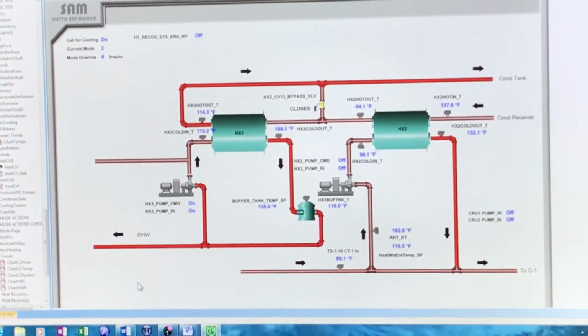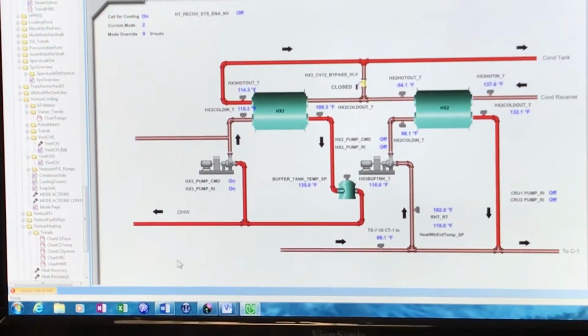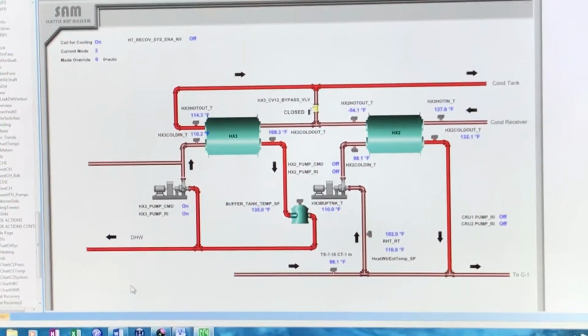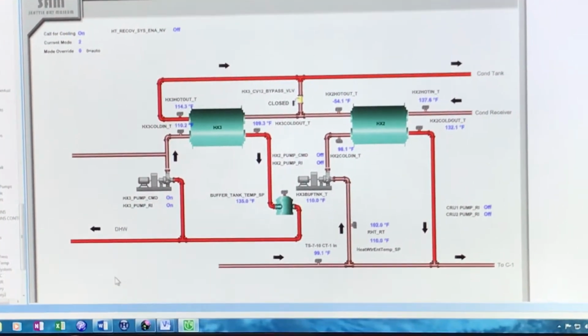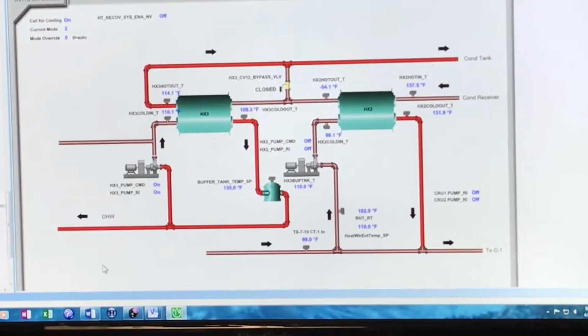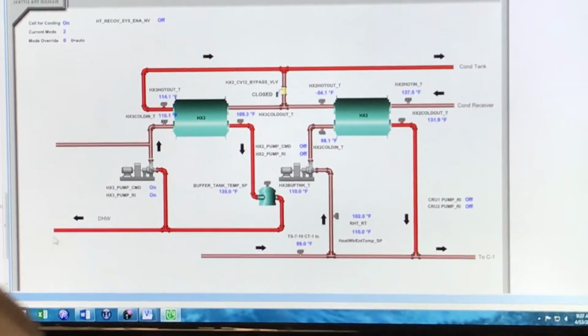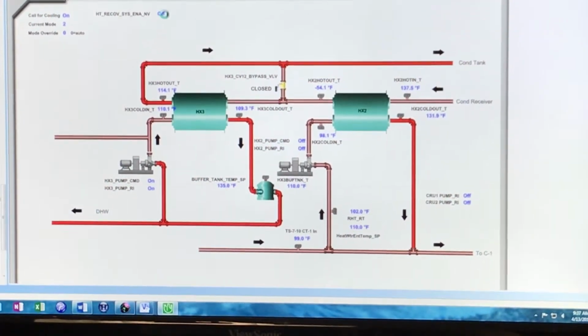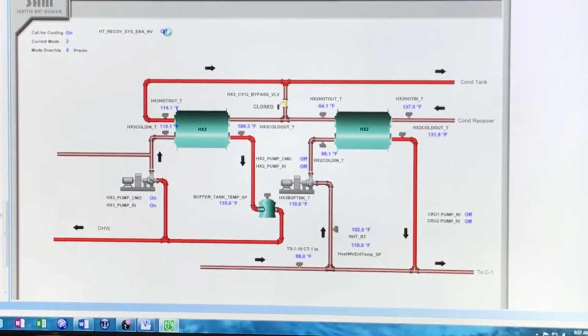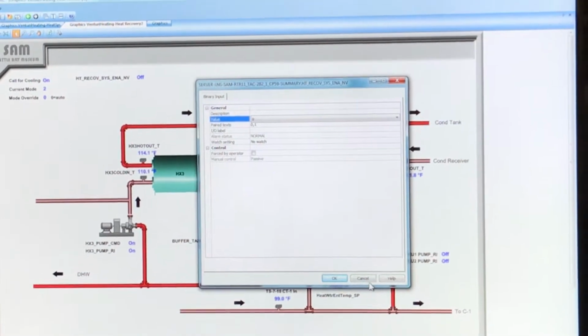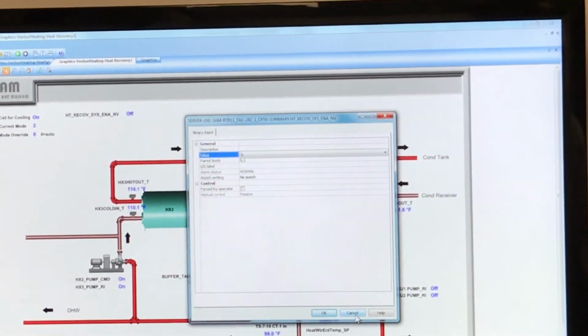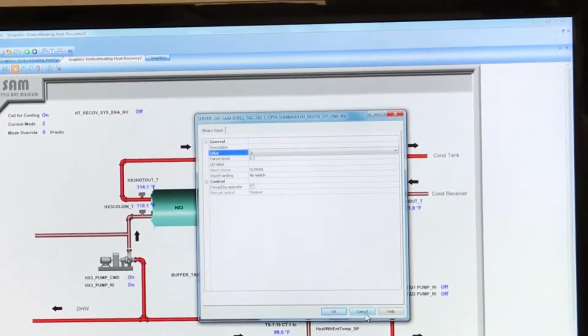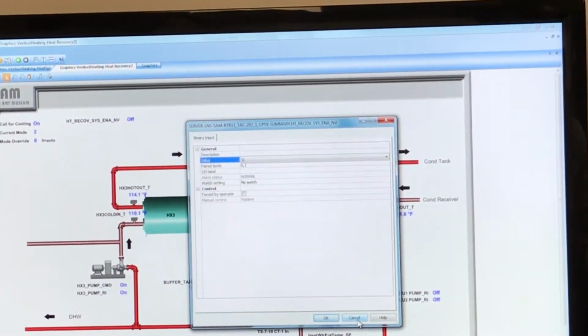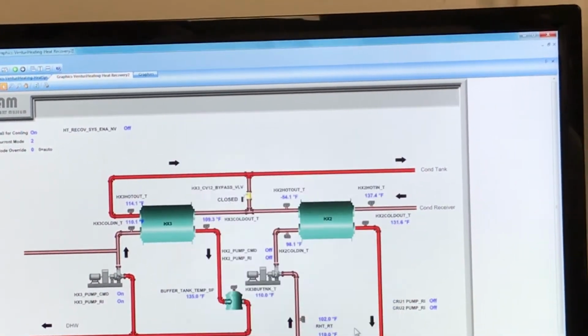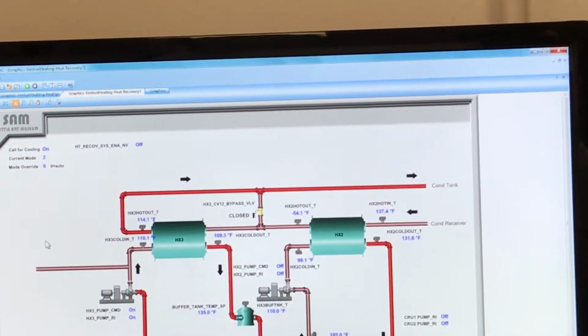It dissipates it. Can you explain? So there's two different kinds. You know what the heat exchangers are? Yeah, the coils in the AC. Well, yeah, but even in these heat exchangers over here, like heat exchanger 1 and 2 back there, they're shell and tube. So you have water going through the coils in there, and you've got steam in the shell. The water's absorbing the heat from the steam, and then you're taking that hot water and putting it out to the building.